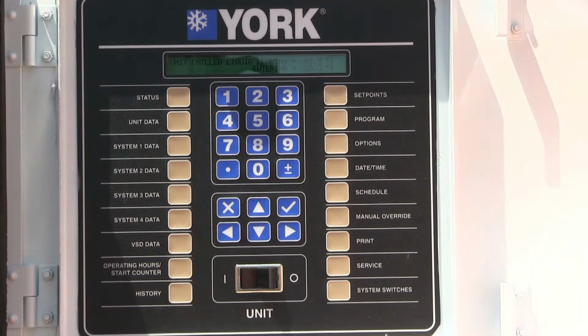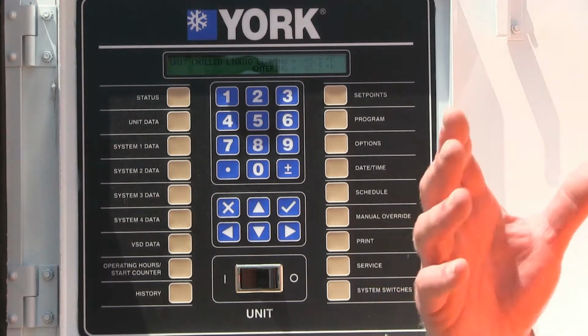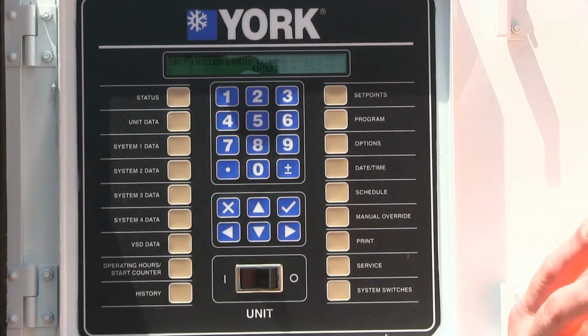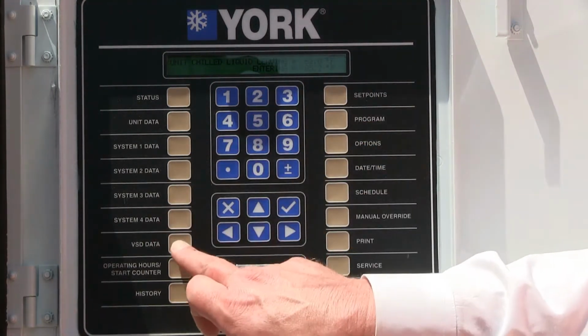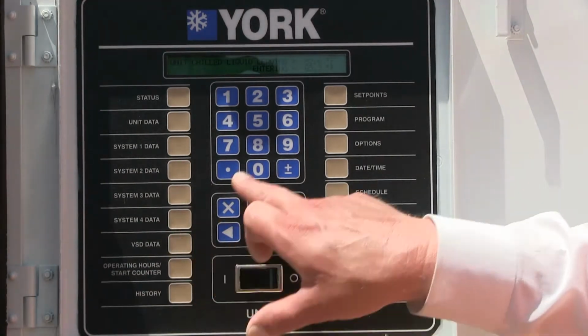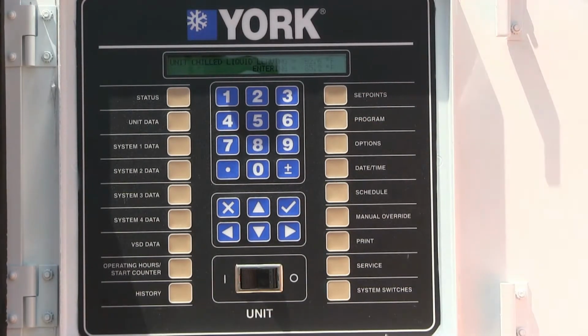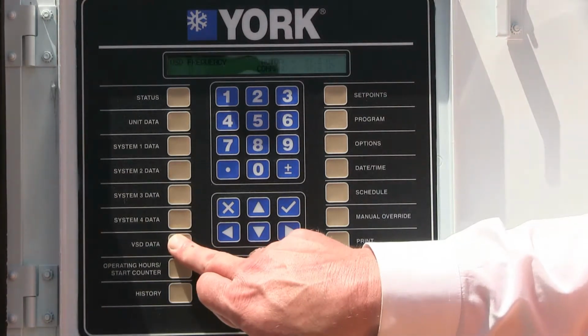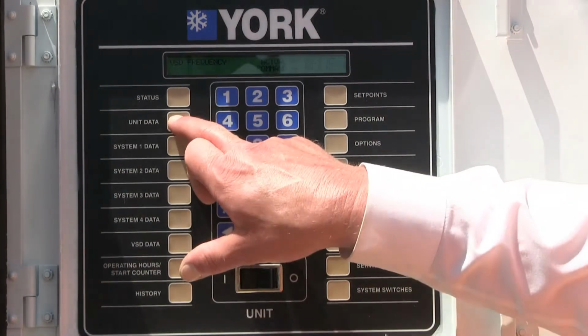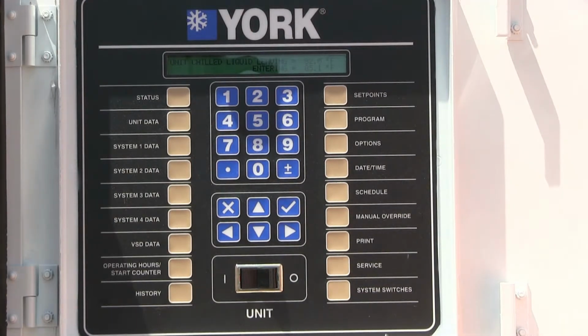We don't have our air handler on yet because we're going to allow the loop to pull down. Anytime you do an installation of these chillers, you want to turn the chiller on and get the entire loop cold. Get it all the way down to set point before you turn your air handler on, so that when you turn the air handler on, the customer gets hit in the face with that nice good cold air. We don't want to start the air handler without having the water cold. When we go back here, you continue to see that our variable speed drive is still ramping up, up to 97 hertz, and our unit data is 82 degrees.